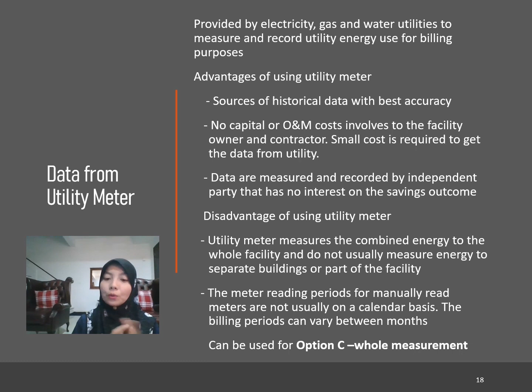But this is not the case today. From my experience, when I look at the TNB bill, most of the time they measure according to the calendar, from the first day of the month to the end of the month. But also from my experience, you must be careful when you do M&V using this utility meter to make sure you look at the period of measurement in the utility bill. There was one case about 2 years ago when TNB issued bills a bit late, covering more than 30 days, because they were changing a meter. So you have to be very careful. Otherwise, your energy data will not be on a monthly basis. As I mentioned earlier, this utility meter is used for Option C, the whole facility measurement.